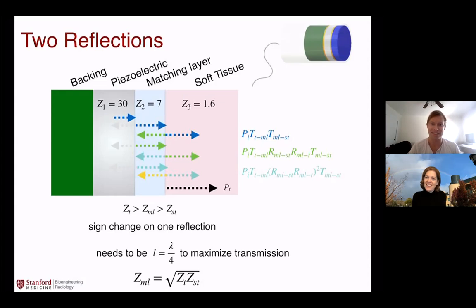I was, yeah. What are you making your matching layers out of? So it was a magnesium alloy, which is very stiff, but a very low density metal. So it sort of fulfilled the acoustic impedance approximately. I mean, there's some wiggle room. If you're not perfectly at the geometric mean or whatever, it's okay, but you try to get as close as you can. Most people use epoxies, I think, doped epoxies for this kind of thing. And so those were your 2 candidates, or did you have other candidates you were looking at? No, those were my 2. And the magnesium alloy just ended up coming in the thickness that I needed, which is around 1 millimeter.